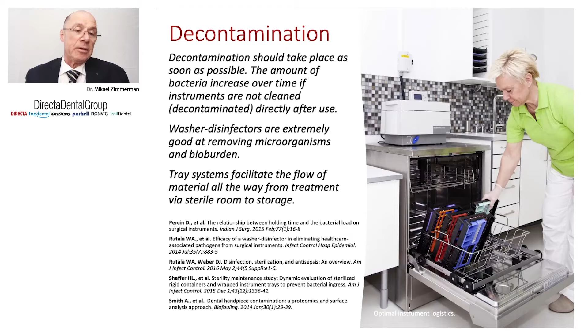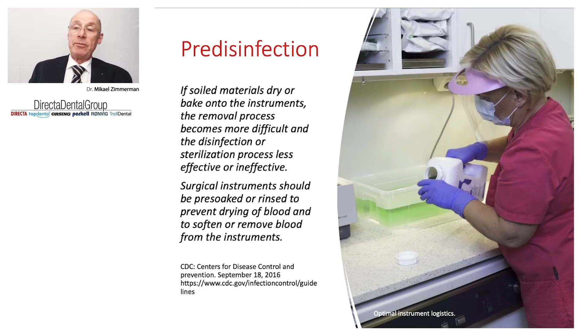Pre-disinfection is an important part. All surgical instruments go through the decontamination phase, which should take place as soon as possible after treatment, best done directly within the treatment room before removing the instruments from the operatory. After decontamination, when the instruments are safe to handle and arrive in the reprocessing area, instruments must be pre-disinfected. They should be pre-soaked and rinsed to prevent drying of blood and to soften and remove both blood and microorganisms and biological debris from the instruments.